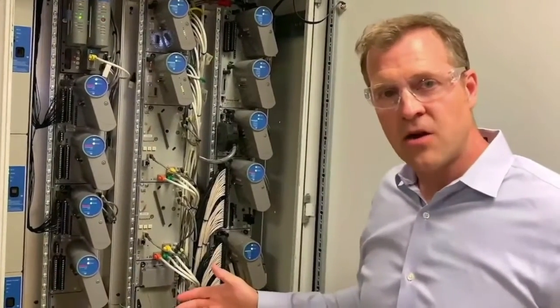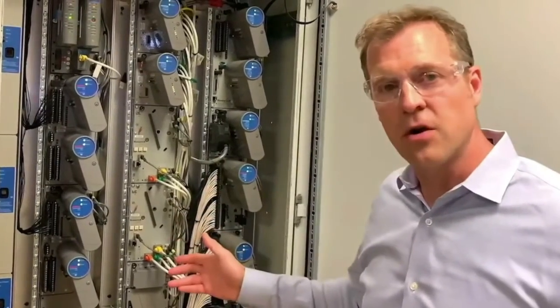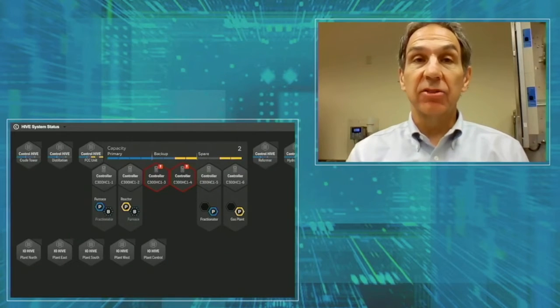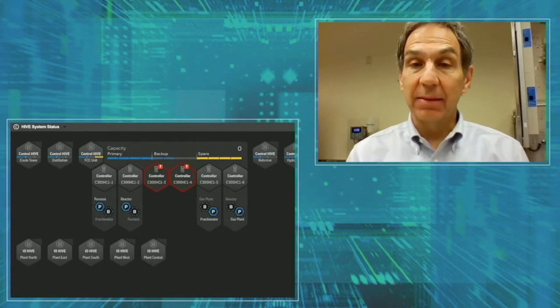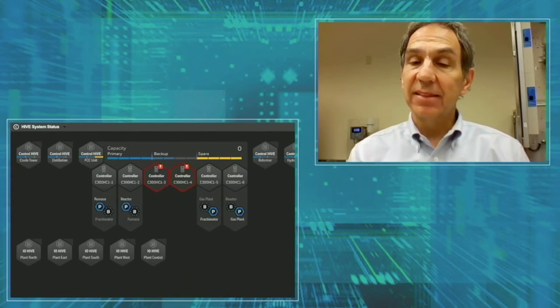No impact to the equipment, no impact to the I/O, and no loss of control. The second incident really illustrates the robustness of the Control Hive. After the second failure, the gas plant control seamlessly fails over, and then backups for the gas plant and reactor CEs are reestablished. At this point, the Control Hive has lost one-third of its compute power and remains completely solid, and is even capable of withstanding yet another bad event.